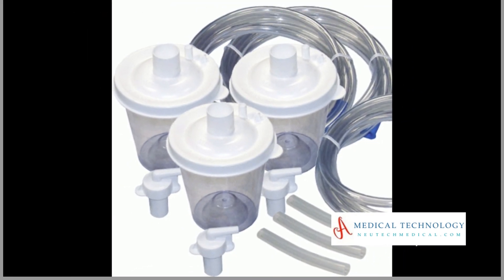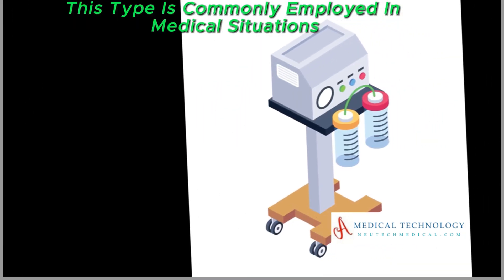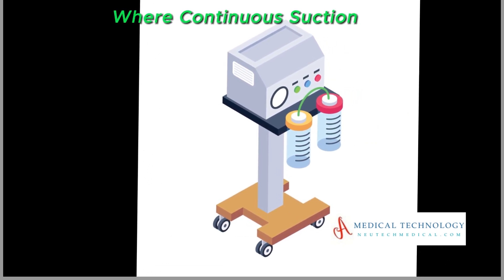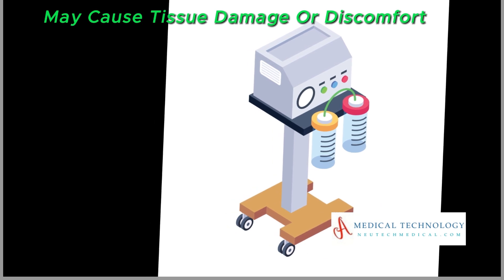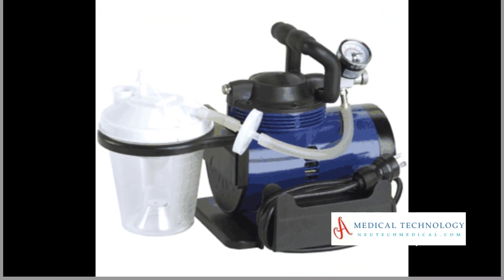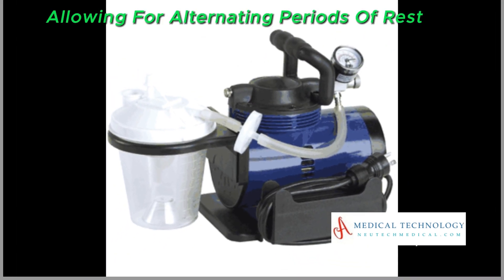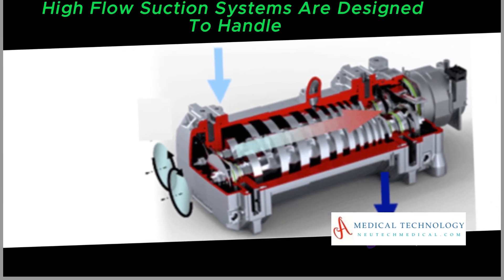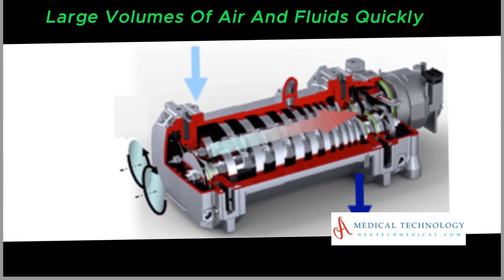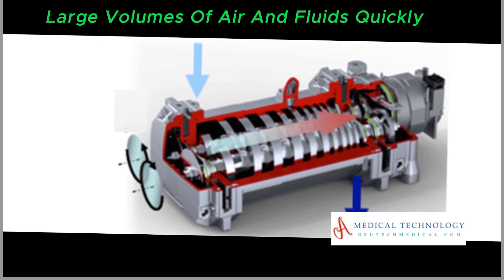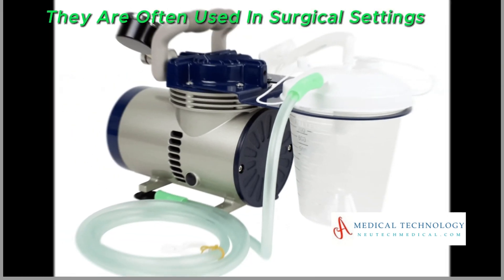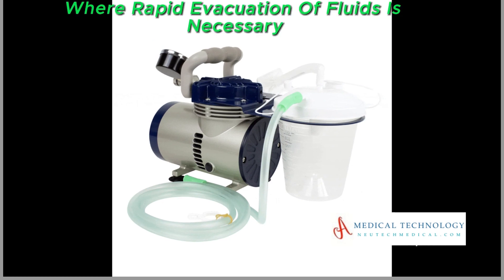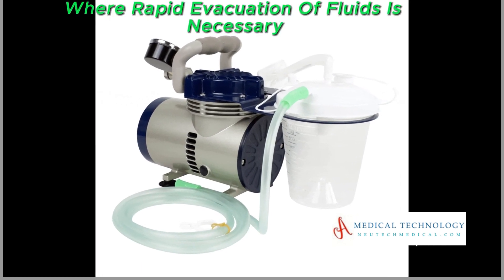Intermittent suction is characterized by the periodic activation and deactivation of suction. This type is commonly employed in medical situations where continuous suction may cause tissue damage or discomfort, allowing for alternating periods of rest. High-flow suction systems are designed to handle large volumes of air and fluids quickly, often used in surgical settings or emergency situations where rapid evacuation of fluids is necessary.